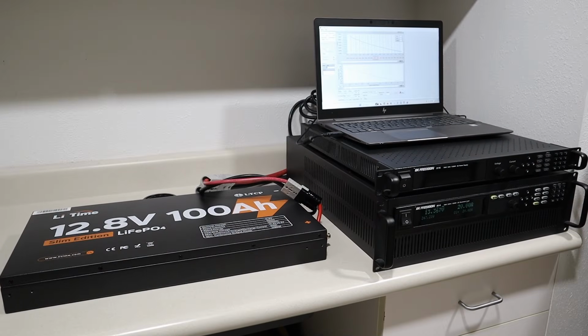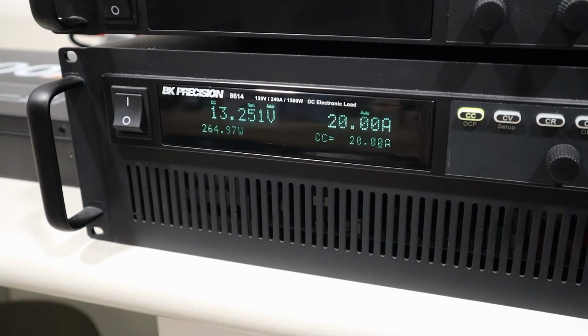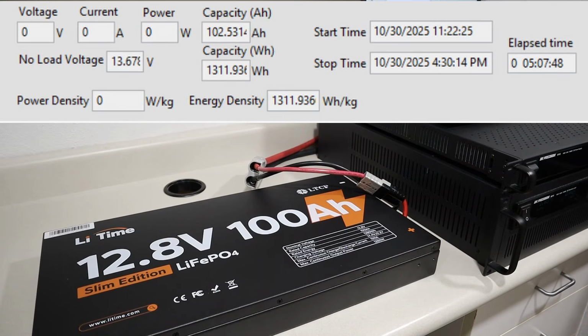First, I completed a capacity test on the battery using my DC electronic load. I had it set to a 0.2C rate, or 20 amps, and by the time the battery had shut off, I pulled a total of 102.5 amp hours, or 1311 watt hours. So we did pull slightly over the full rated capacity of the battery, at 102%.